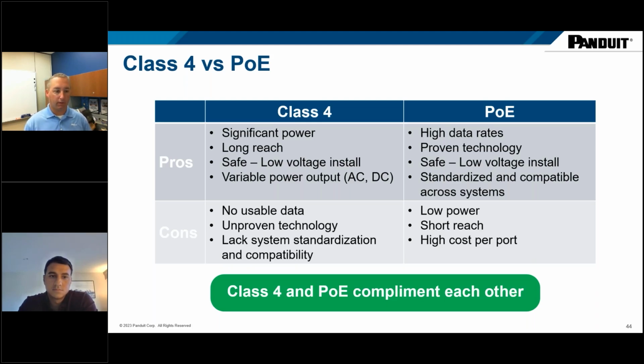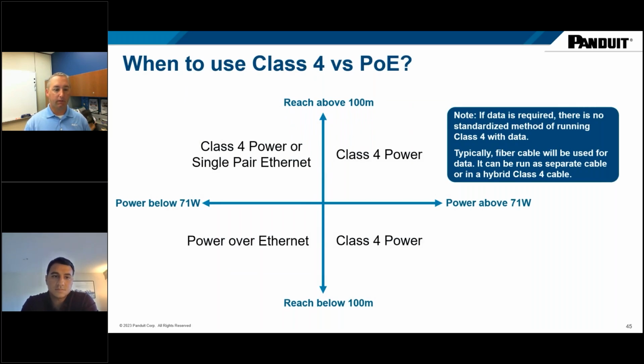Go to the next slide. So when to use one or the other? First, I give a disclaimer. If data is required, there's no standardized method of running class 4 with data. You can use a fiber cable, because the fiber cable will complement the reach of class 4, and it can be run separately or within a hybrid cable. The way I have it broken up is very simple. If the reach is above 100 meters, depending on how much power you need, it's going to be either a class 4 power system or something that may use single pair Ethernet, depending on how much power is needed.